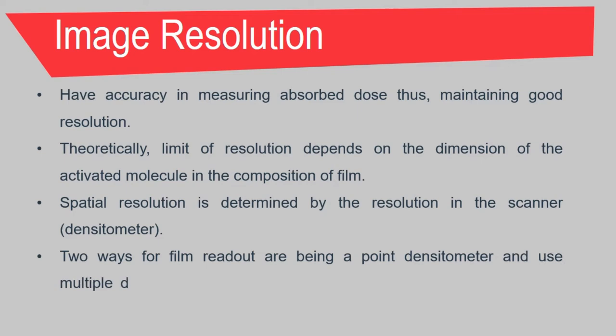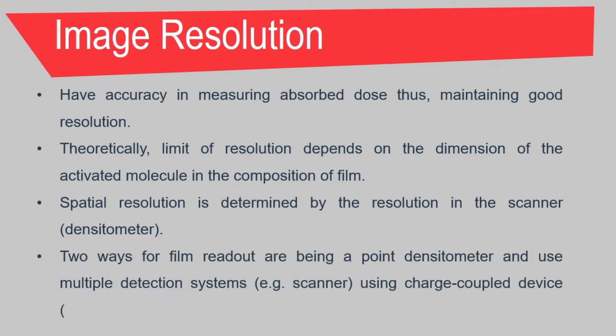RCF has accuracy in measuring absorbed dose while maintaining good resolution. Theoretically, the limit of resolution depends on the dimension of the activated molecule and the composition of the film. Spatial resolution is determined by the resolution in the scanner. The two ways for film readout are using a point densitometer and using a multiple detection system using a charge-coupled device.